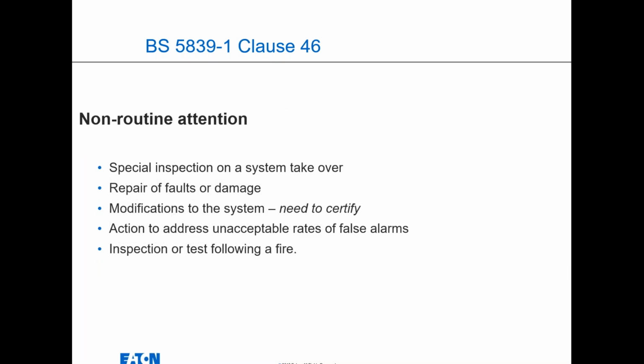Some of the non-routine inspections: that's a special inspection if you take over a system, repairs or any faults or any damages, any mods that you make, and again that can be put through the verification certificate, and actions to address any issues with false alarms, and inspection or test following a fire.